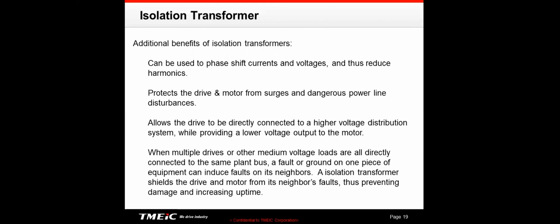Next, when multiple drives or other medium voltage drives are all directly connected to the same plant bus, a fault or a ground on one piece of equipment can induce faults on its neighbors.